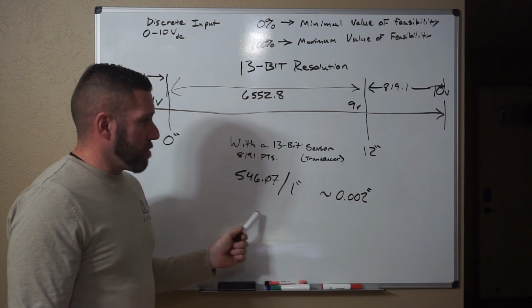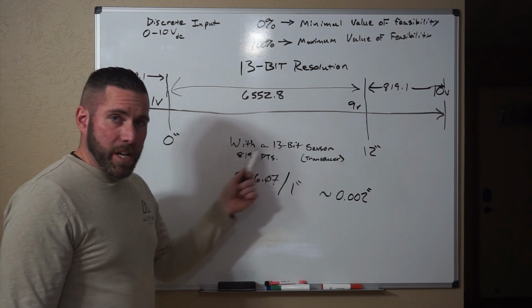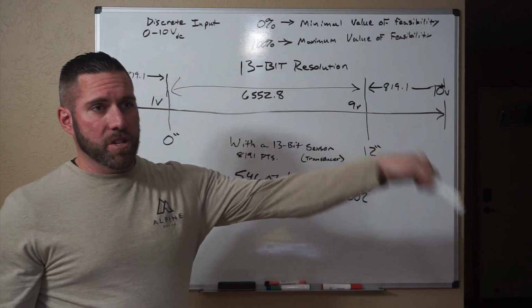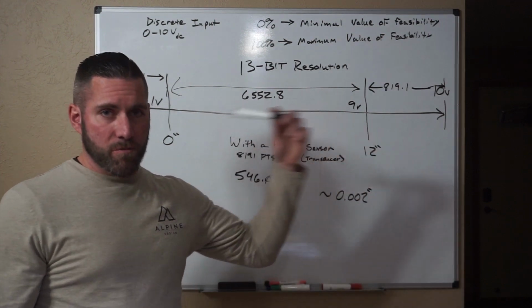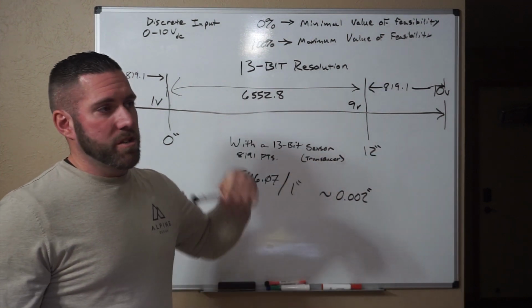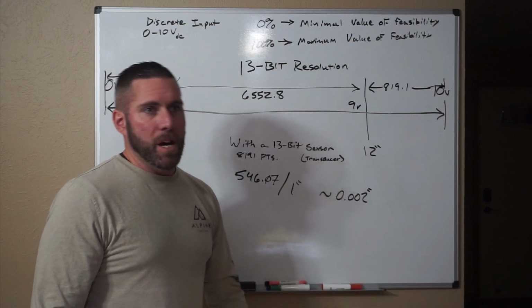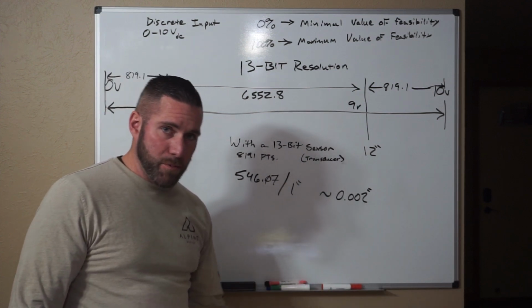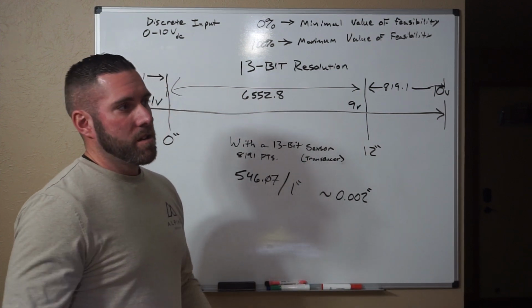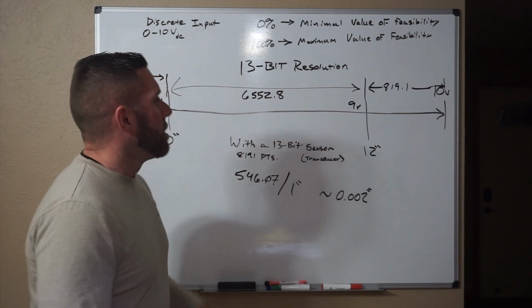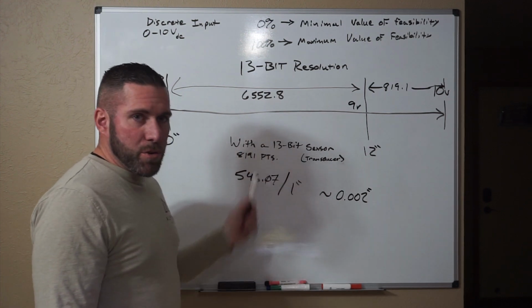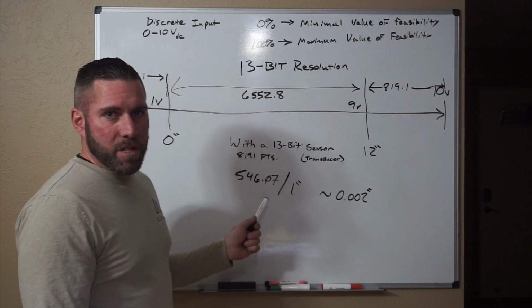So when you read this stuff, make sure you're reading it at the sensor. Work your way from the signal source to the signal receiver, checking connections. Make sure you don't have inductive feedback on your lines. Make sure they're not in a bad cable tray to ground. Know the difference between earth and ground. Things like that play a huge role in diagnosing problems with these things.